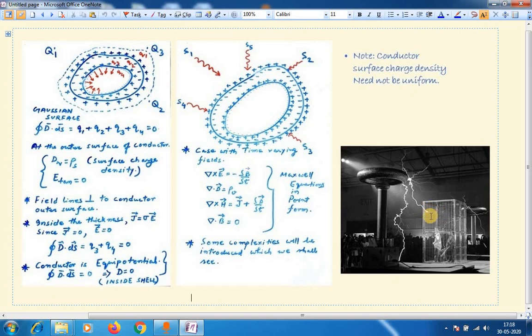Now when we have a cage like structure as shown here, what it will do is it will distribute this current into smaller current elements, isn't it? Smaller current elements, and what this will do is we won't have a high potential difference between any 2 points because the current is getting distributed into smaller paths, isn't it?